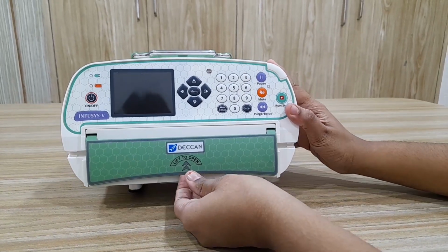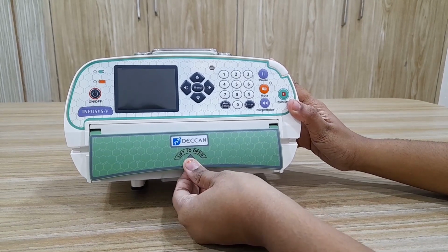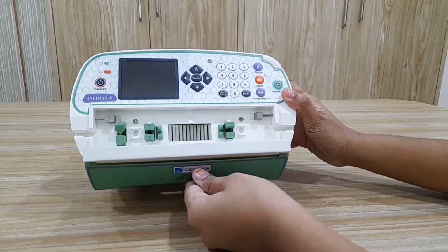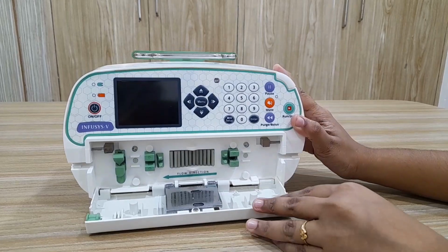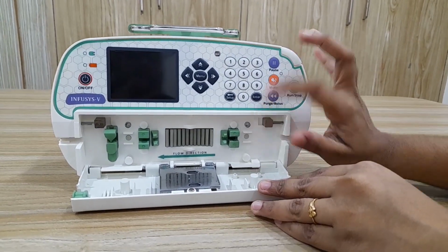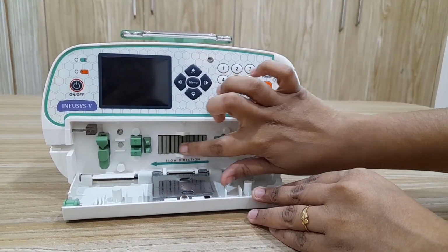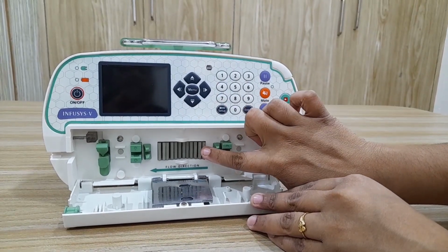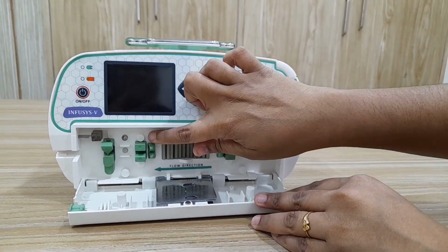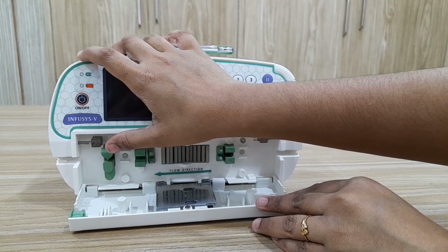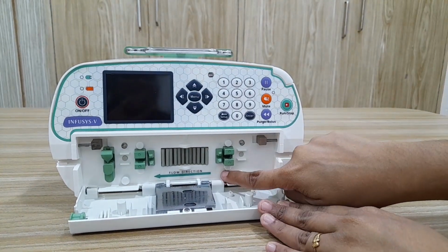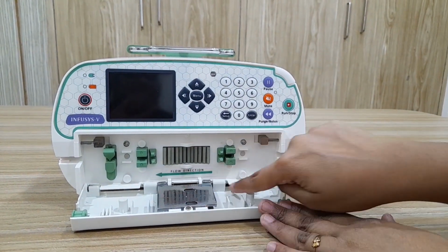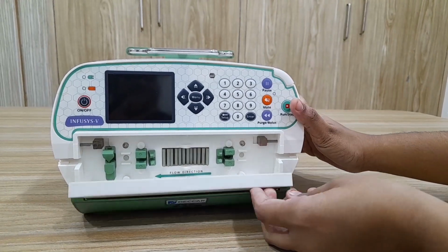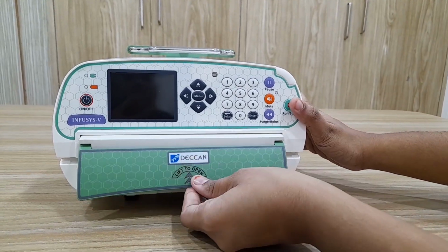Now we can open the door using the door latch. Lift the door latch and open the door gently. Here we can see the air bubble sensor, cam plate for peristaltic movement, and occlusion pressure sensor, as well as the anti-free flow mechanism. As per the flow direction, we have to place the IV set. Once the IV set is placed, kindly close the door.